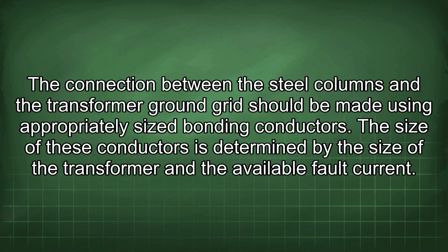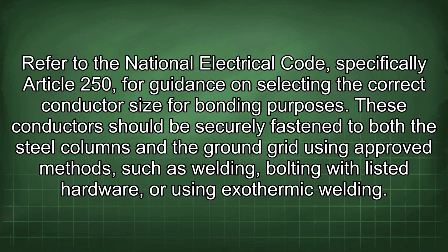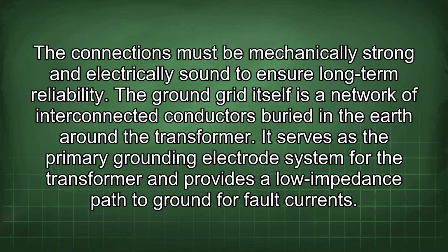The connection between the steel columns and the transformer ground grid should be made using appropriately sized bonding conductors. The size of these conductors is determined by the size of the transformer and the available fault current. Refer to the National Electrical Code, specifically Article 250, for guidance on selecting the correct conductor size for bonding purposes. These conductors should be securely fastened to both the steel columns and the ground grid using approved methods, such as welding, bolting with listed hardware, or using exothermic welding. The connections must be mechanically strong and electrically sound to ensure long-term reliability.